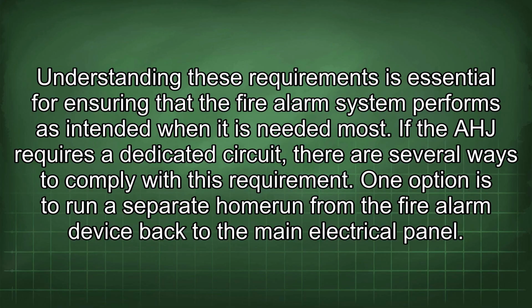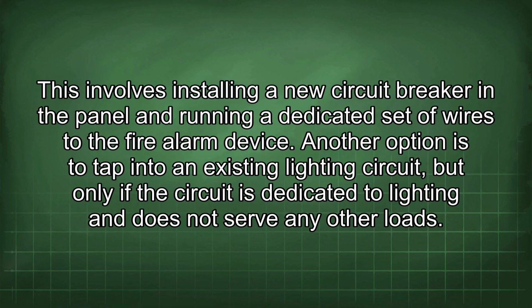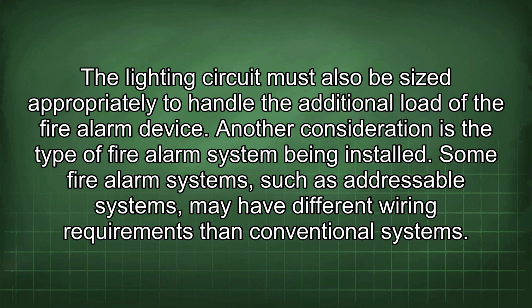If the AHJ requires a dedicated circuit, there are several ways to comply with this requirement. One option is to run a separate homerun from the fire alarm device back to the main electrical panel. This involves installing a new circuit breaker in the panel and running a dedicated set of wires to the fire alarm device. Another option is to tap into an existing lighting circuit, but only if the circuit is dedicated to lighting and does not serve any other loads. The lighting circuit must also be sized appropriately to handle the additional load of the fire alarm device.